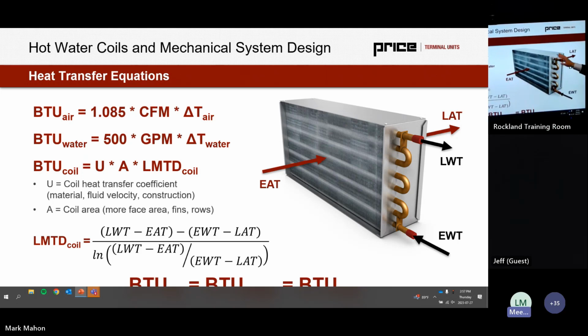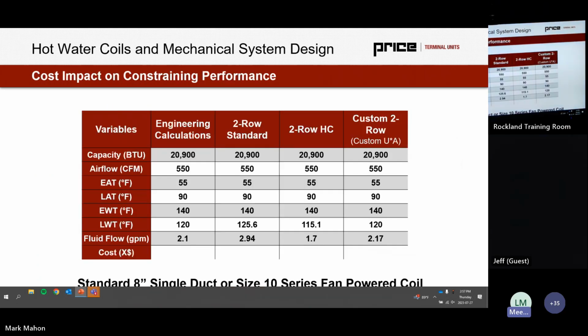So if I took a coil and I could make it any size with any material, I could always match the air side and the water side equation. And I actually did that. We can create custom coils at Price. We can also purchase very custom coils from manufacturers. But what I wanted to compare was the engineering calcs: a 2-row standard coil and a 2-row high capacity coil. This is for a 10 and 12 fin per inch condition. That's what standard and high capacity means from Price.